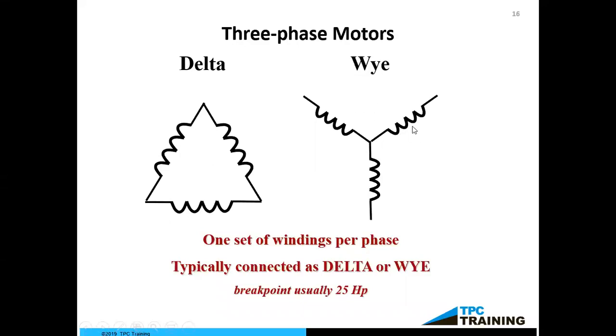The Y configuration to the right gives us better speed control. So depending on what we need in our facility, do we need something with a lot of torque? Is it a slow-moving crane or whatever? Or do we need something that has great speed control? That would make a determination of the motor that we want to purchase. And the cutoff usually for this is right near 25 horsepower. Above 25 horsepower, you're going to see a lot of delta wound motors. Below 25 horsepower, you're going to see a lot of Y wound motors.